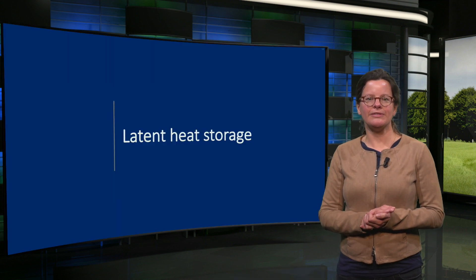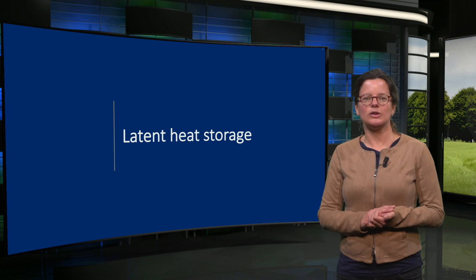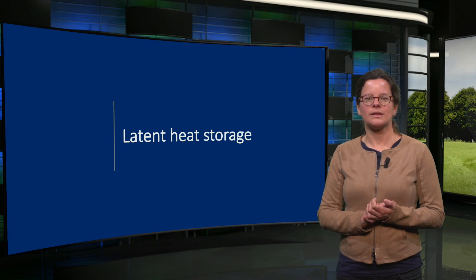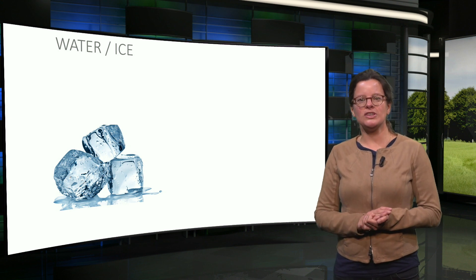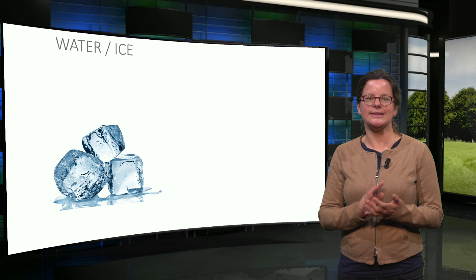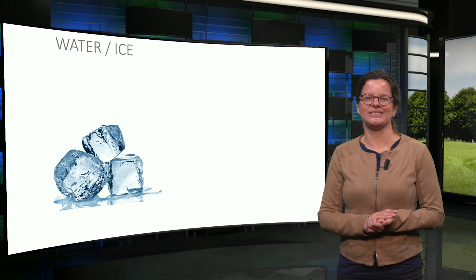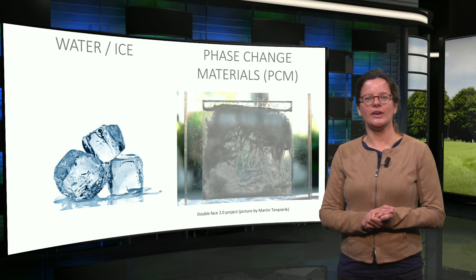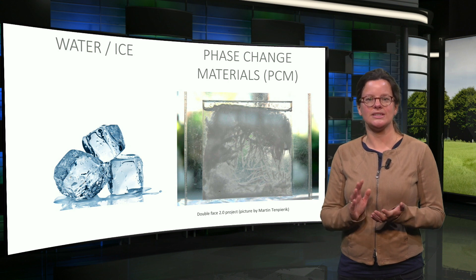I would like to briefly mention latent thermal energy storage. In the change of phase of a material, for example from liquid to solid or from solid to liquid, a lot of heat is required or released. This phenomenon can be used to store energy. The most well-known phase change material is water. In the phase change from water to ice, the energy released is 80 times as much energy as cooling down the same amount of water with 1 degree Celsius. For the built environment, various other types of phase change materials have been developed and are still being developed, which usually have a higher melting point, meaning much energy can be stored at these temperatures.